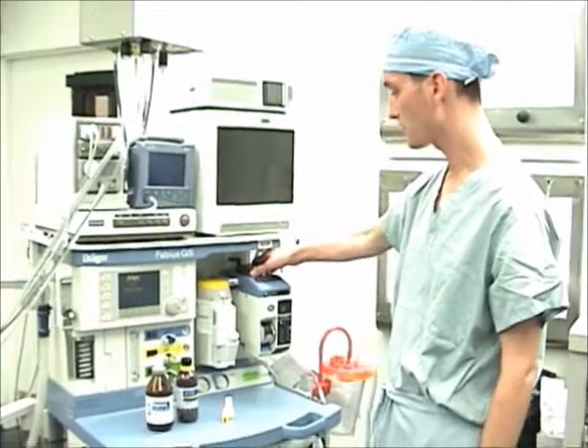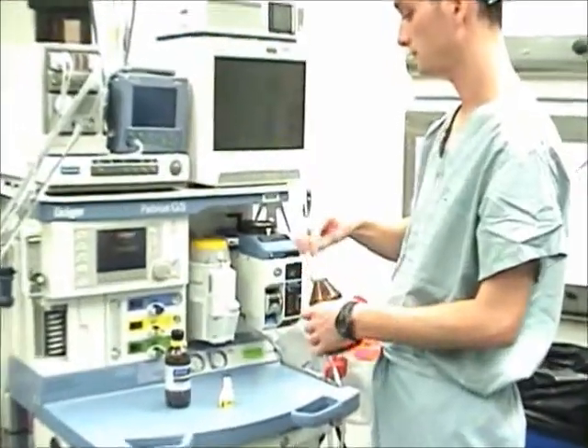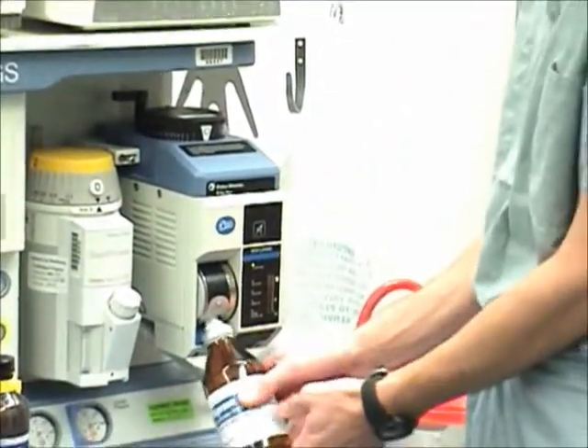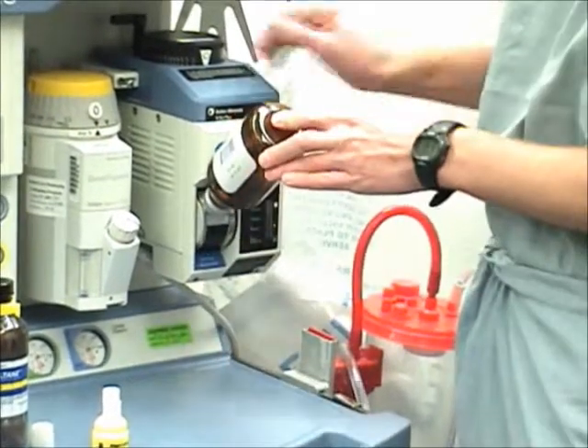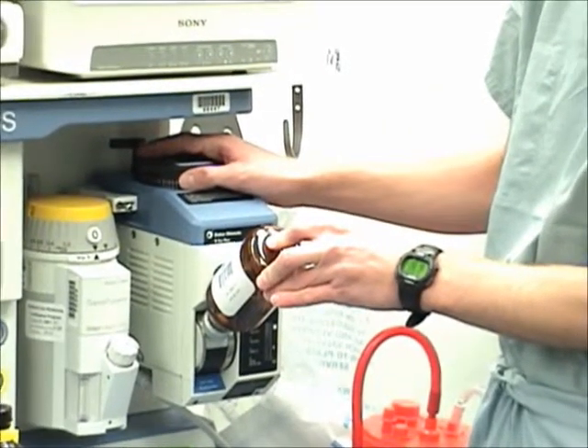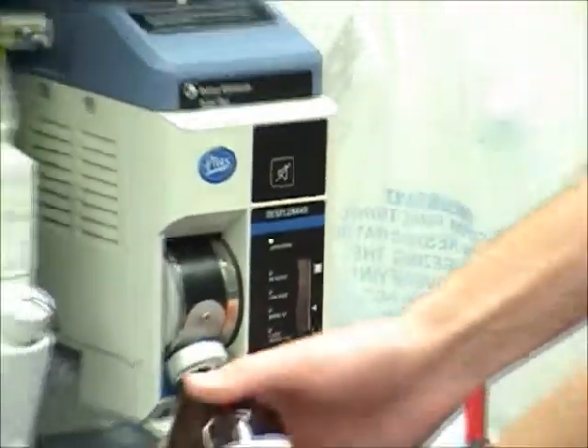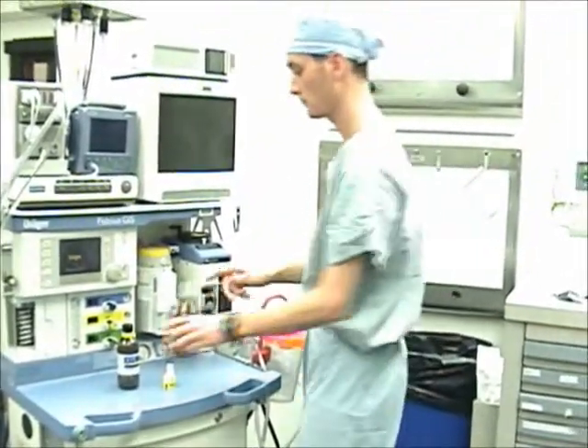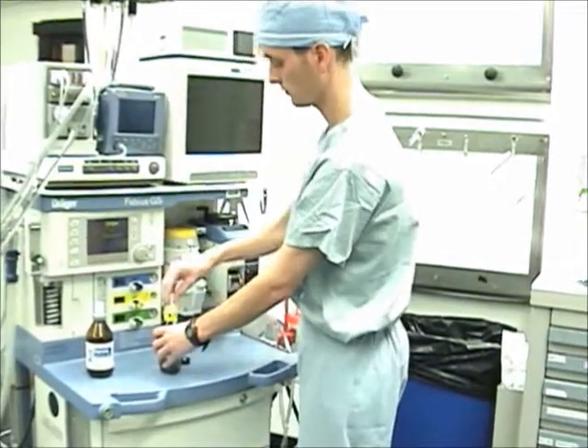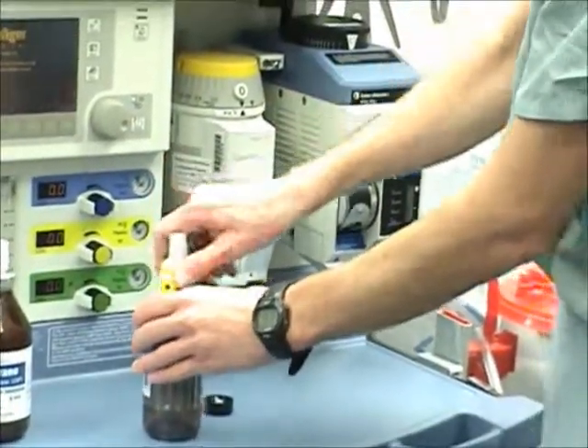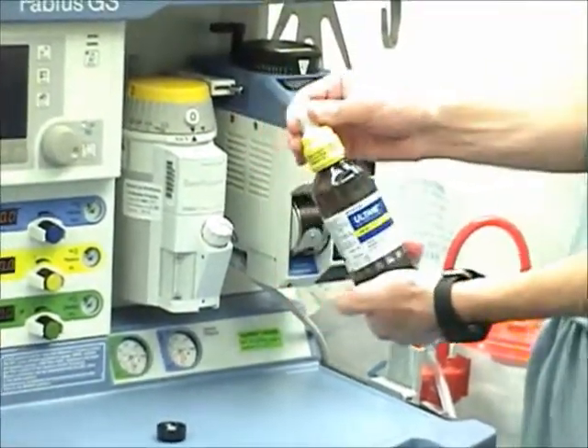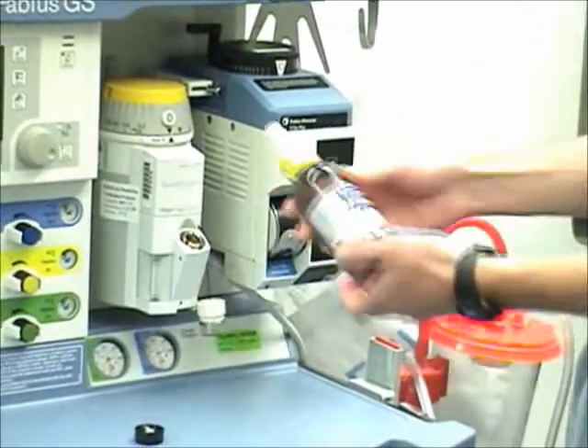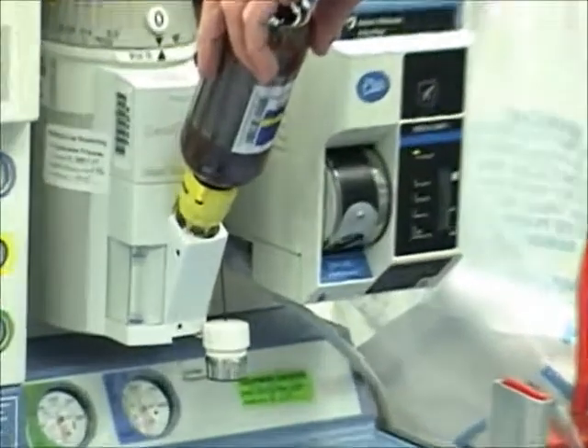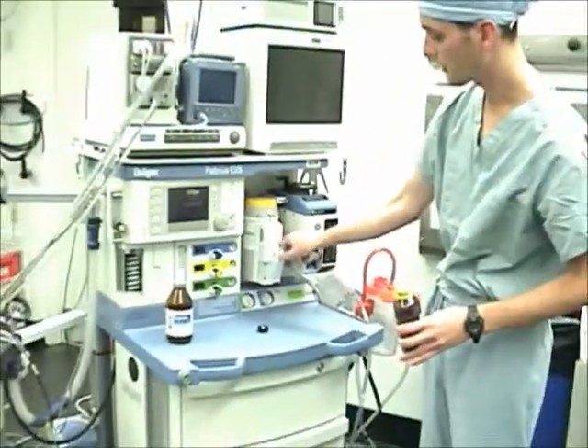To fill the vaporizer, ensure that the vaporizer dial is set to 0. A fill mark on the vaporizer indicates when it's full. When filling the vaporizer, a special adapter is usually required. The fill line indicates this vaporizer is full.